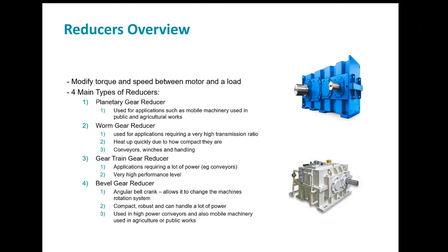Worm gear reducers are generally used for applications requiring very high transmission ratios. The mechanism is non-reversible, meaning the worm wheel cannot drive the worm. The advantage of this non-reversible mechanism is that it ensures a greater level of security for the system. Worm gear reducers are less expensive than planetary gearboxes and are also quieter. Like planetary gearboxes, worm gear reducers heat up quickly due to how compact they are and have variable performance levels. These are generally used for conveyors, winches, and handling.